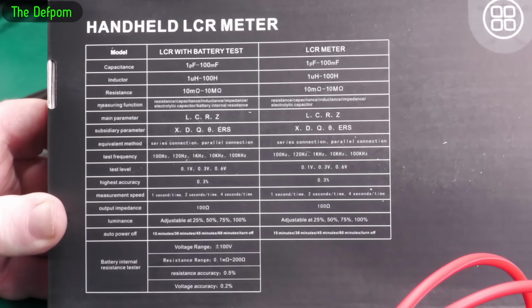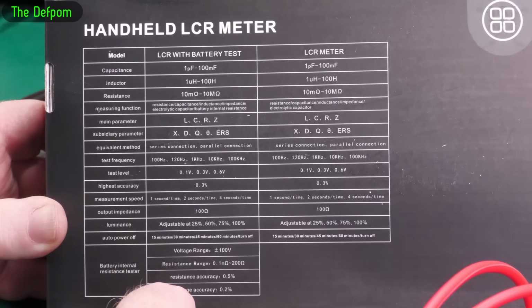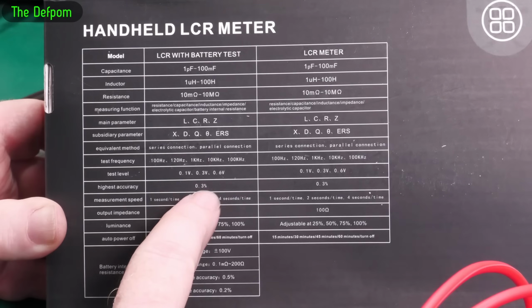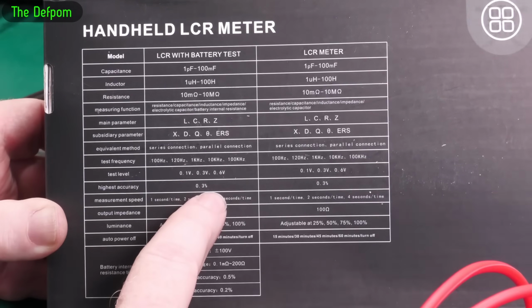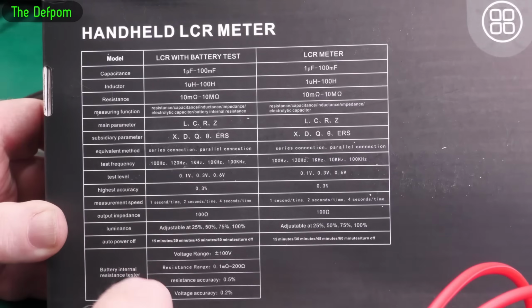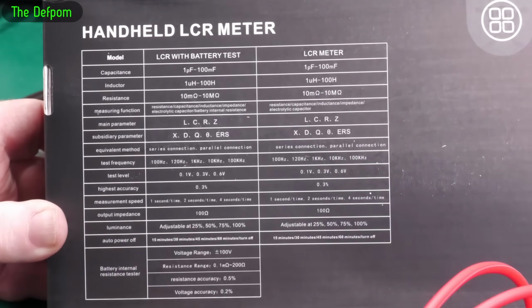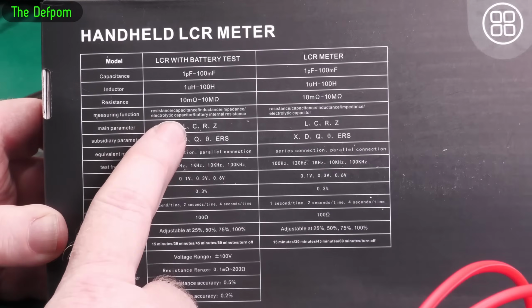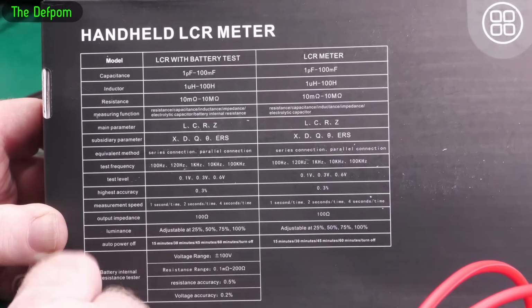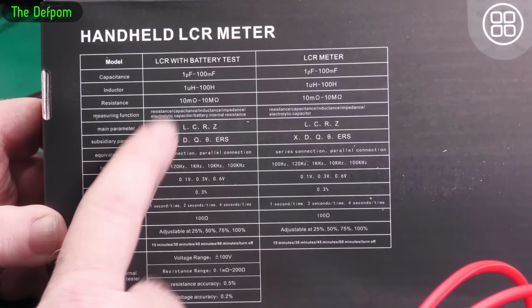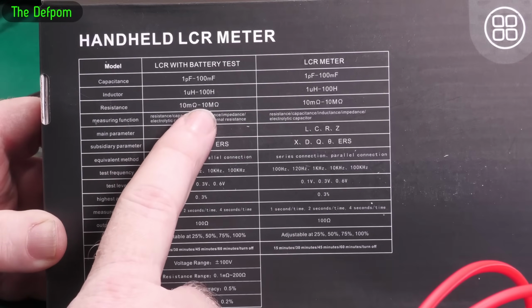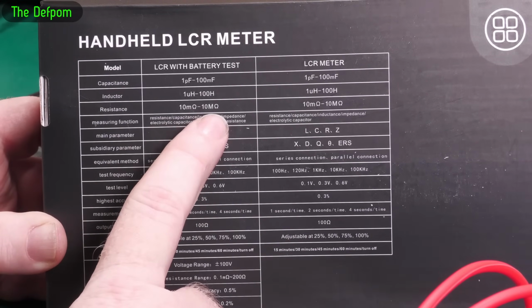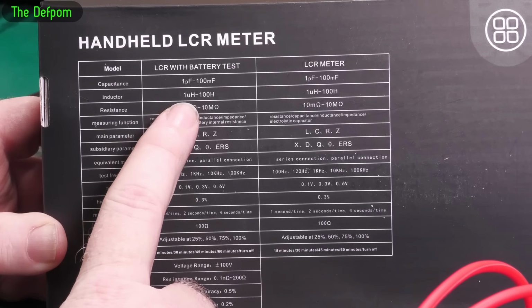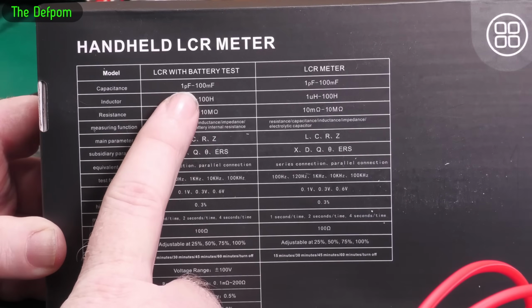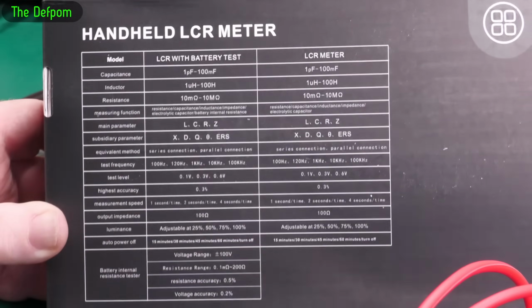So that's all the information you need to know: test frequencies, accuracies. The highest accuracies aren't necessarily the best case, and depending on what you're doing it can be up to 5% depending on what you're measuring and how. It measures LCR and Z, plus secondary parameters as most LCR meters do. You can go from 10 milliohm to 10 meg, 1 microhenry to 100 henries, and 1 picofarad to 100 millifarads.